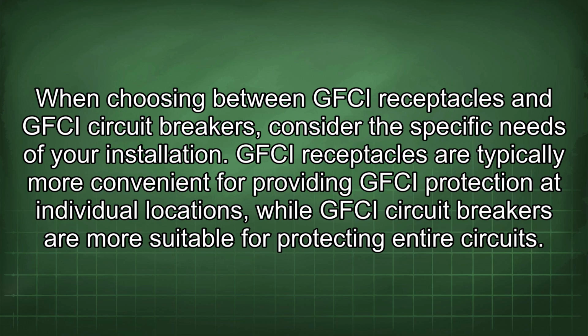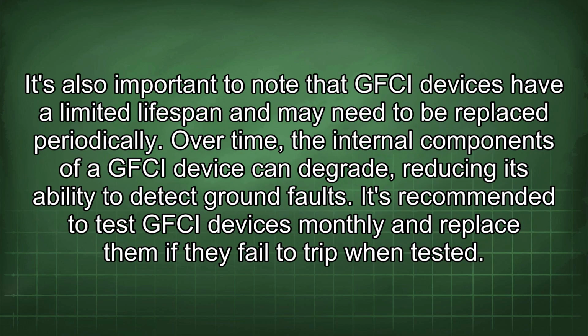for protecting entire circuits. It's also important to note that GFCI devices have a limited lifespan and may need to be replaced periodically. Over time, the internal components of a GFCI device can degrade, reducing its ability to detect ground faults. It's recommended to test GFCI devices monthly and replace them if they fail to trip when tested.